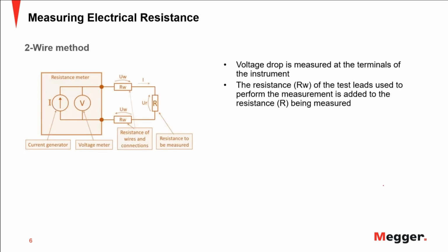So let's get a little bit more detail, and there's a method called the two-wire method. This is basically what I was showing in the previous slide, but with a little bit more detail. You still have your current generator, you have your voltage meter, and this shows the leads connecting from the instrument to the resistance under measurement. Those leads have a resistance. Definitely they're not perfect conductors, so they're going to have a resistance.